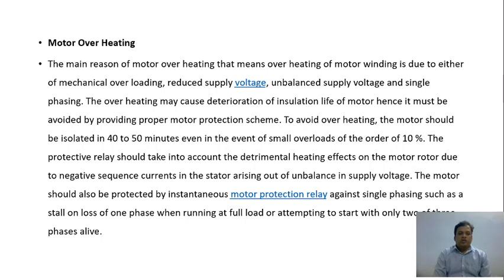So the protective relay should take into account the detrimental heating effects on the motor rotor due to negative sequence currents in the stator arising out of unbalance in the supply voltage. So if there is unbalance in the supply voltage, then these negative sequence currents in the stator will cause the motor to overheat. The motor should also be protected by an instantaneous motor protection relay against single phasing, such as a stall on loss of one phase when running at full load, or attempting to start with only two of three phases alive.